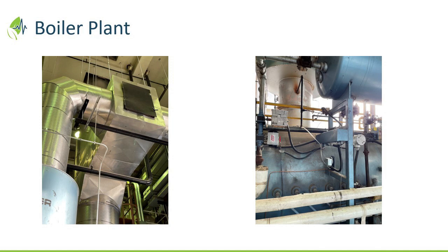Yeah. When I have a mic, I also have a question, not regarding the economizer, but about tube failure. So the coil tube sometimes fails, and by the time you notice, it's too late. So is there any indication where you can find out if your coil is failing? Because sometimes it's too late when you open the boiler and find it. Is there an indication?